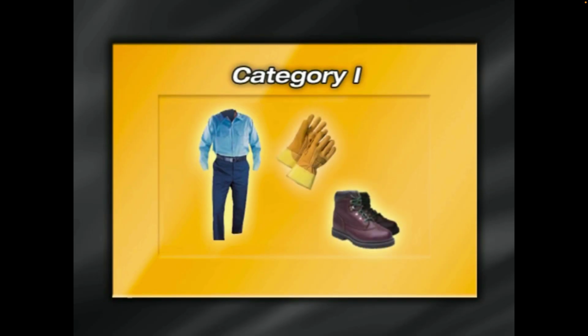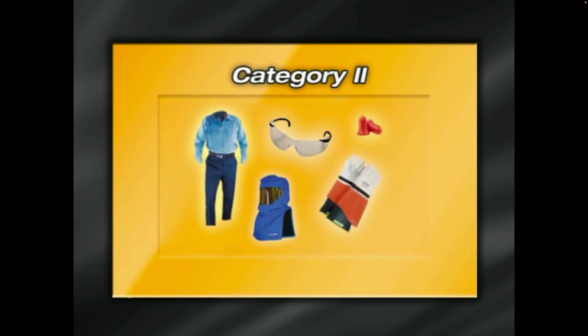Voltage testing on energized parts increases the risk hazard level to 2+. For this job, you need a natural flame-resistant t-shirt under your flame-resistant shirt and natural fiber trousers under your flame-resistant pants or coveralls. You need safety glasses or safety goggles under a double-layer switching hood. Earplugs, voltage-rated gloves with leather protectors, and tools are also required.